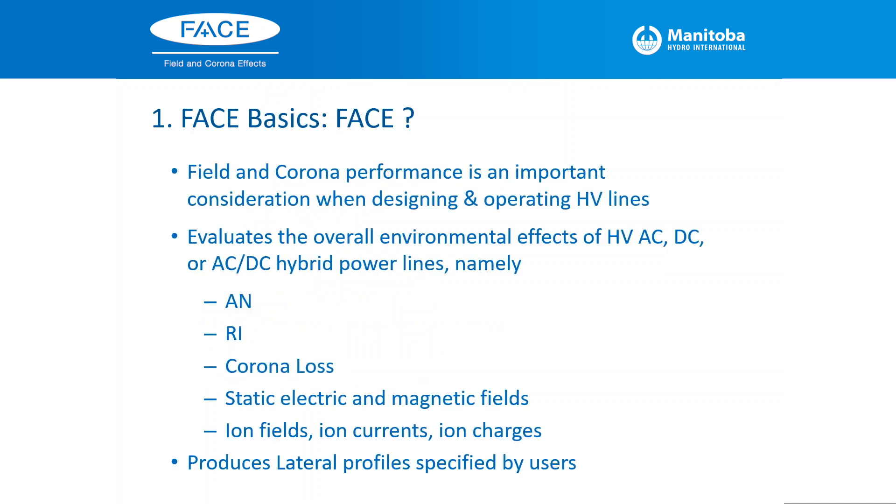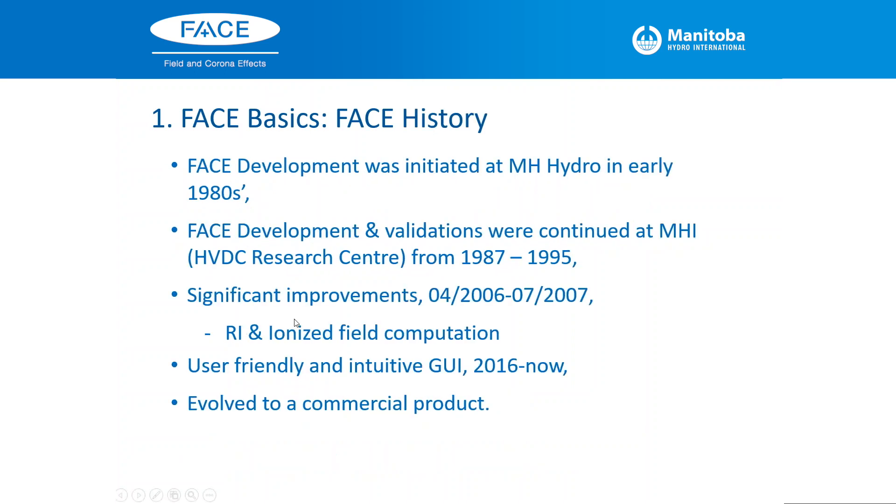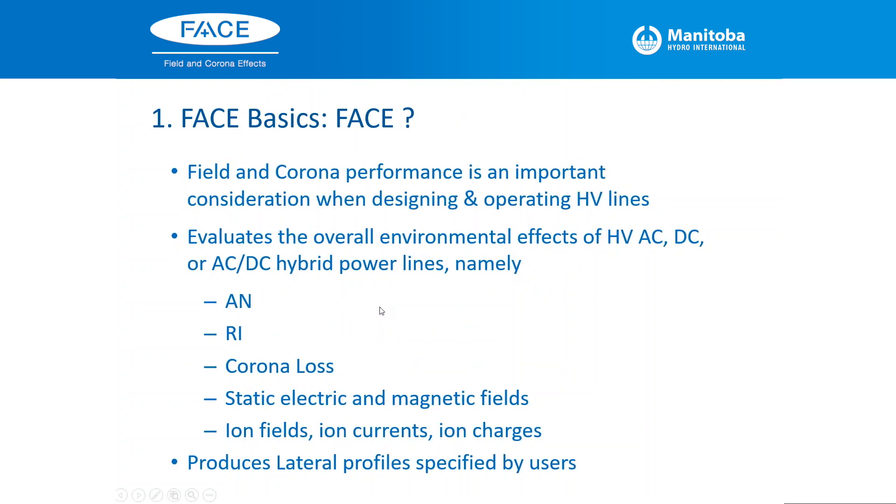FACE basics: Field and corona performance is an important consideration when designing and operating high voltage transmission lines. Evaluating the overall environment effect of HVAC, DC or AC-DC hybrid power lines, namely audible noise, radio interference, corona loss, static field and magnetic field. Ion field computation is one of the big issues. FACE is able to handle all ionized field computations, including ion field, ion current and ion charge. It also produces lateral profiles that can be specified by the users.